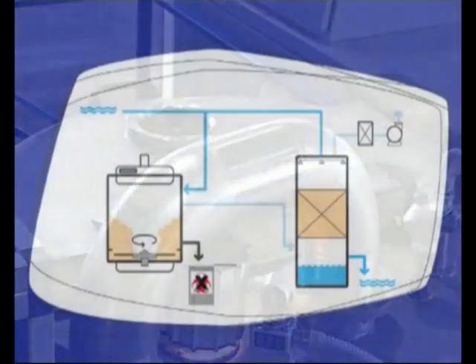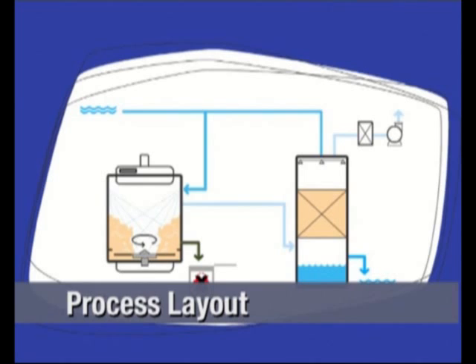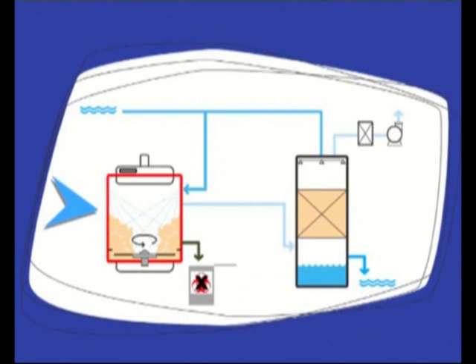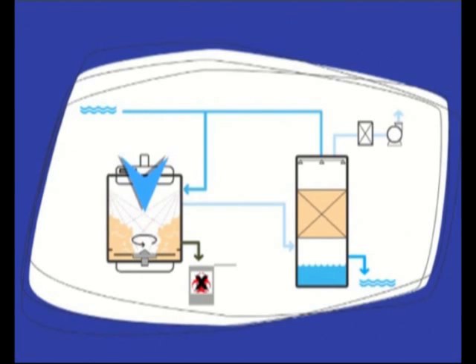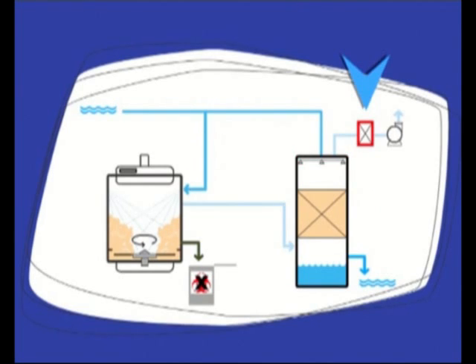The innovative character of the process is that sterilization will be obtained in any case, no matter the type of waste. All the process is done in a sterilization cell. Material temperature is continuously monitored by an infrared reader. A liquid disinfectant is used to sanitize the air tubes at the end of each cycle. A scrubber cleans up smoke, preventing any particles in suspension from escaping. A pump maintains the system in constant negative pressure to make it impossible for infected air to escape into the environment. A filter system cleans the outgoing air with an efficacy of 99.999%.